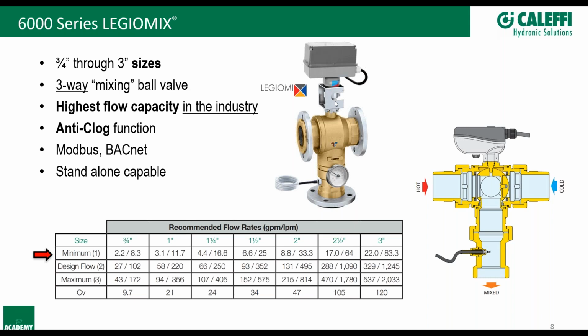If you're controlling at a lower temperature through your distribution system, you'll have less heat being lost to ambient. For example, if ambient in the building is 70 and your pipe is 120 versus 140, you're going to have more heat loss off a 140-degree pipe than a 120-degree pipe. But I don't think payback is the right word—I think safety and protection of the occupants is first and foremost.